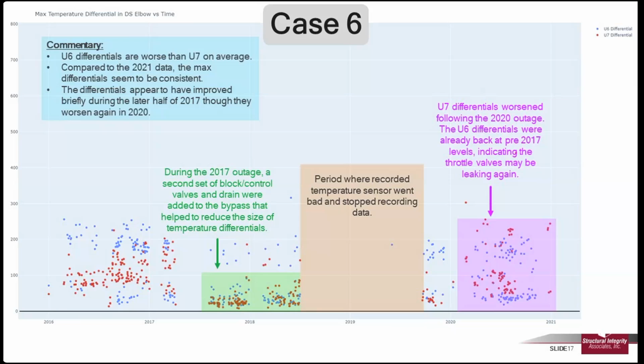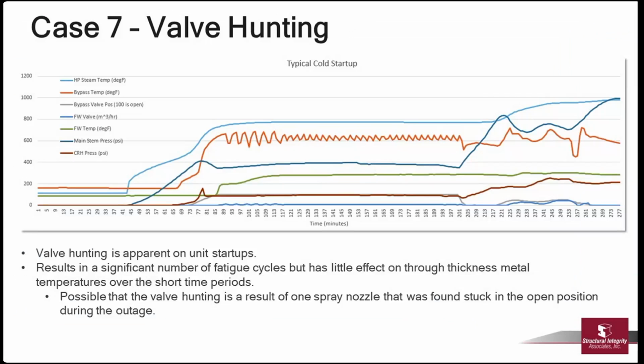So certainly this plant is still installing additional instrumentation to more accurately determine what exactly is going on and what leads to these differentials on startups. But just from having a limited set, it provided them valuable data to see a trend in these differentials that would drive damage.